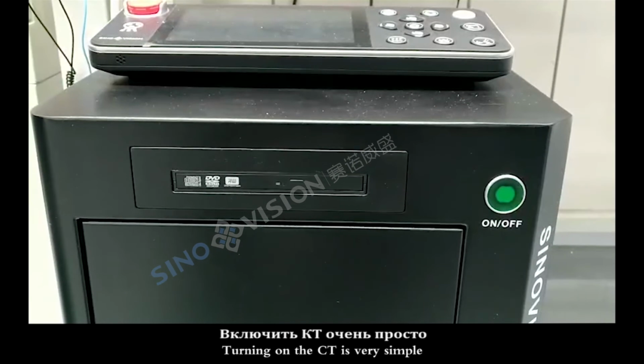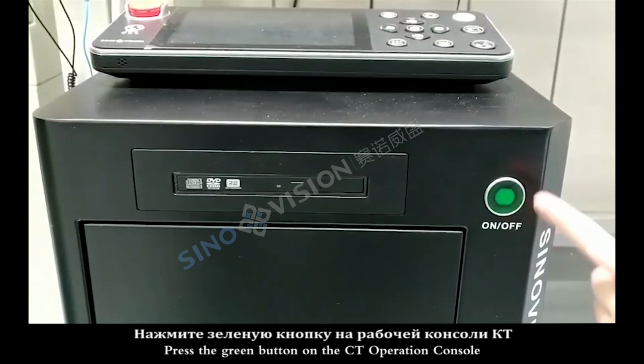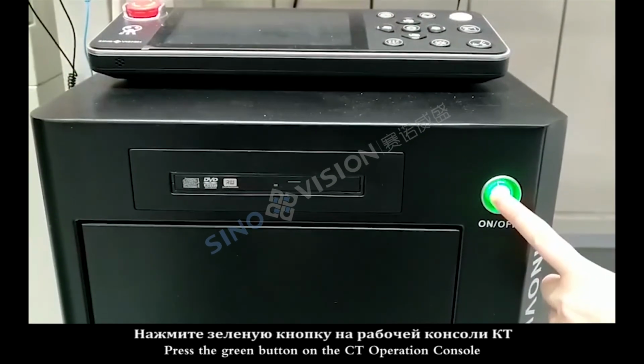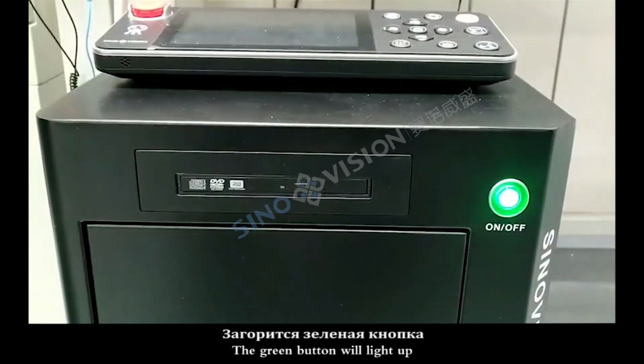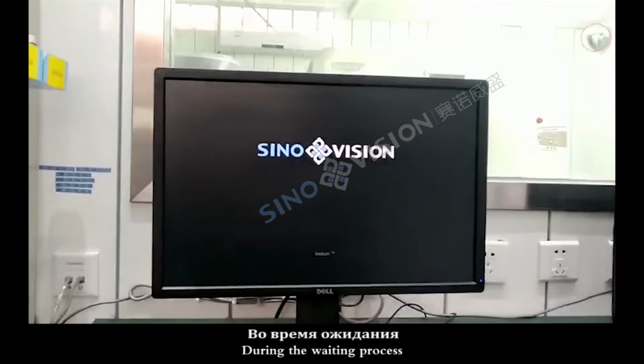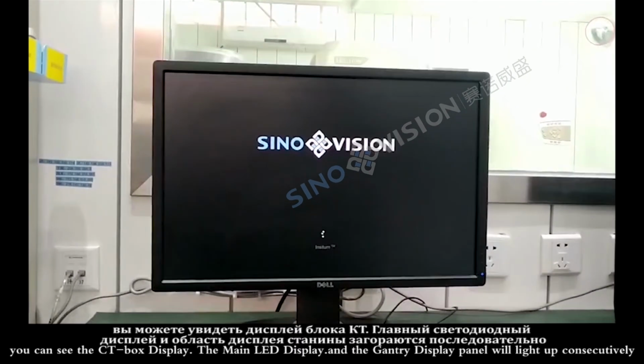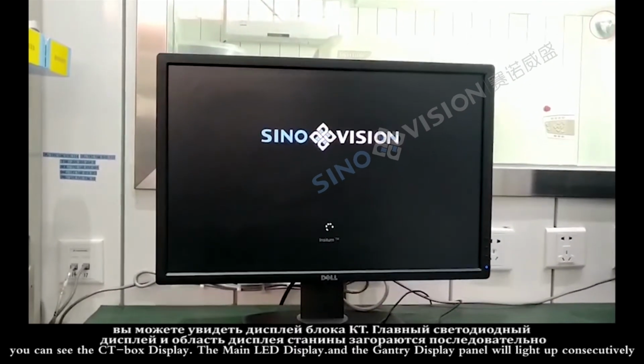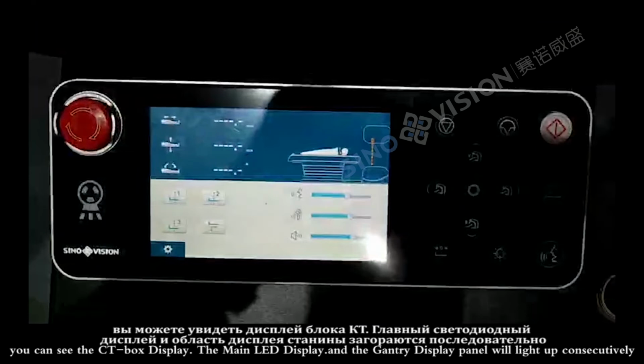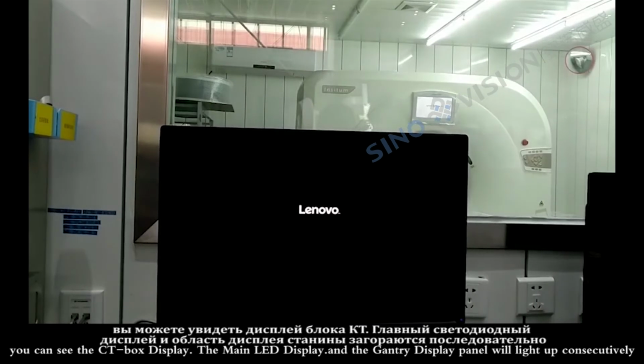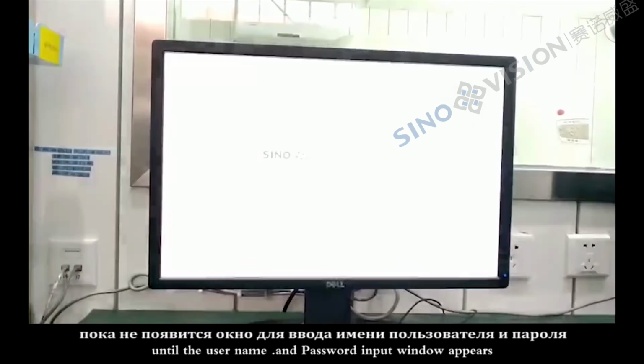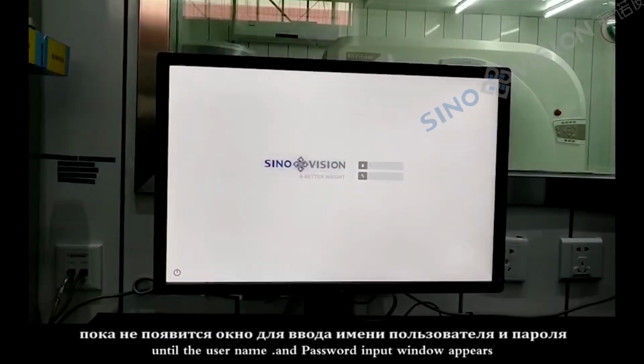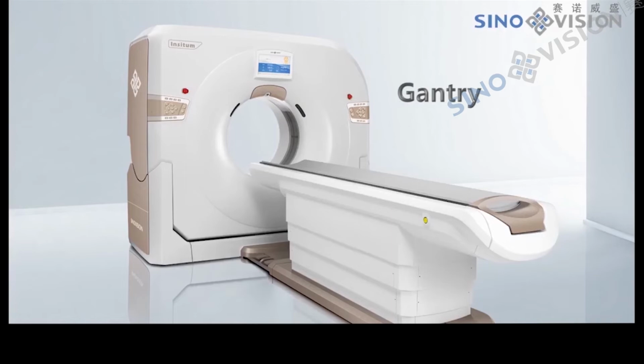Turning on the CT is very simple. Press the green button on the CT operation console. The green button will light up during the waiting process. You can see the main LED display, the CT box display, and the gantry display panel will light up consecutively until the username and password input window appears.